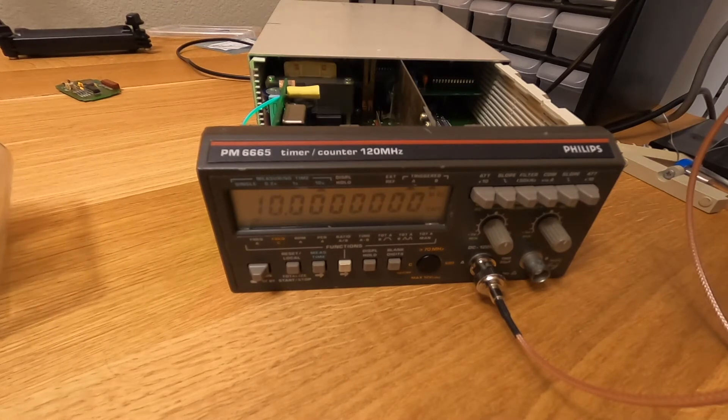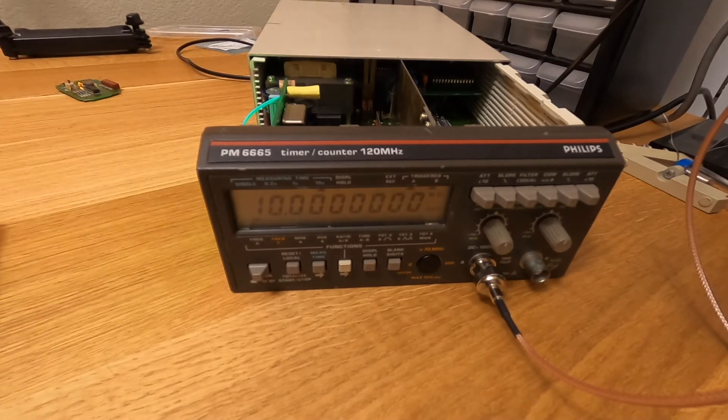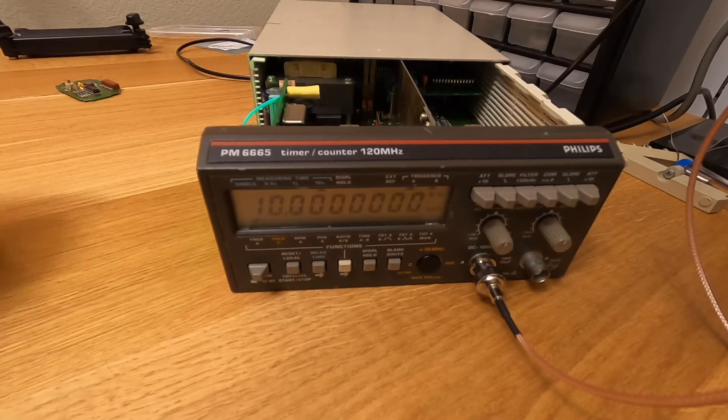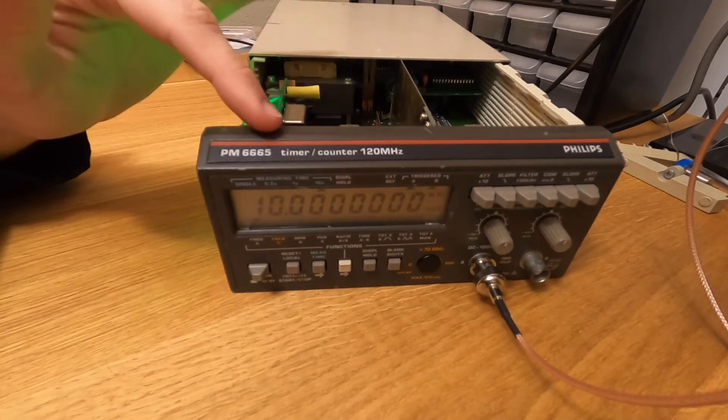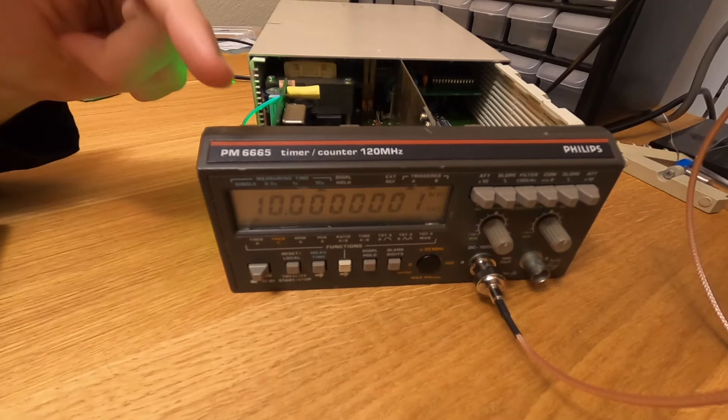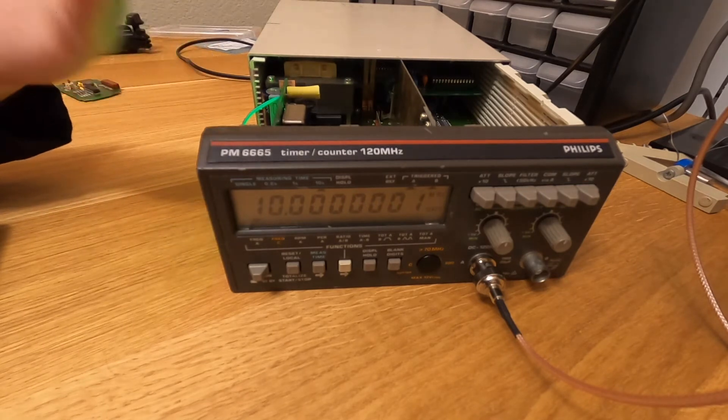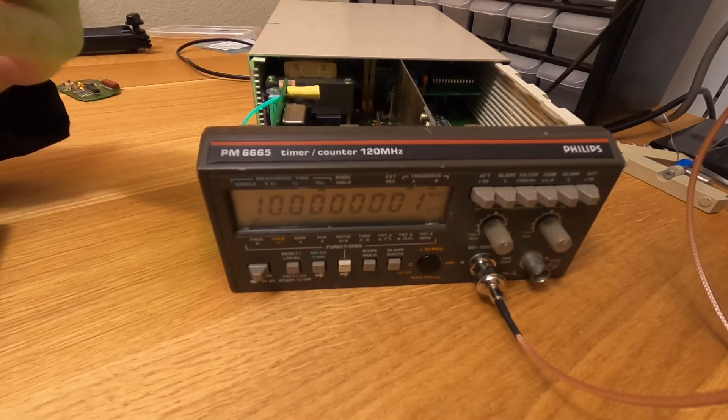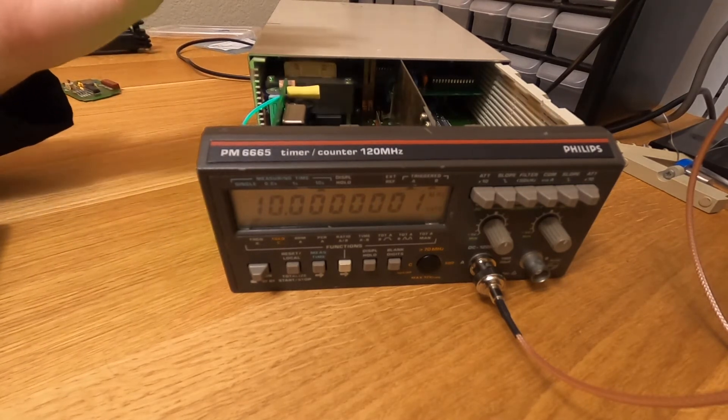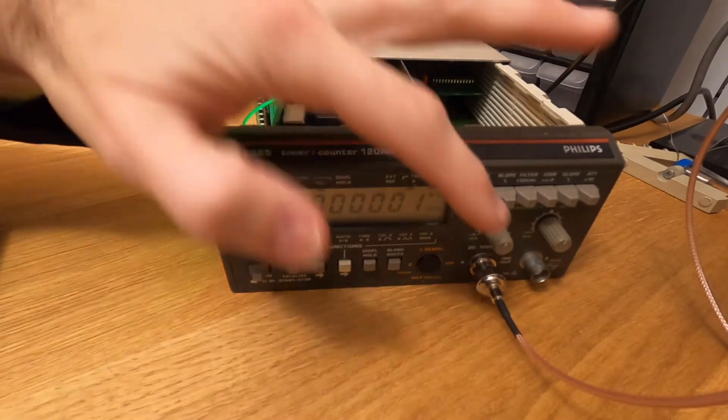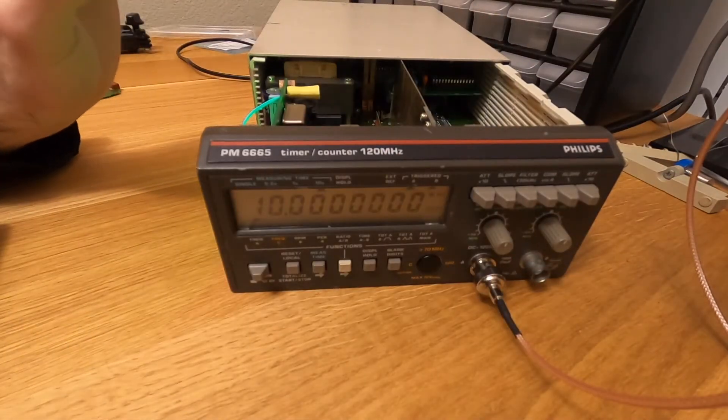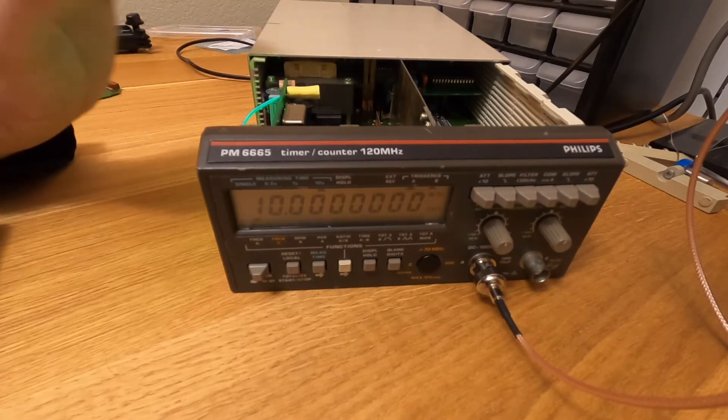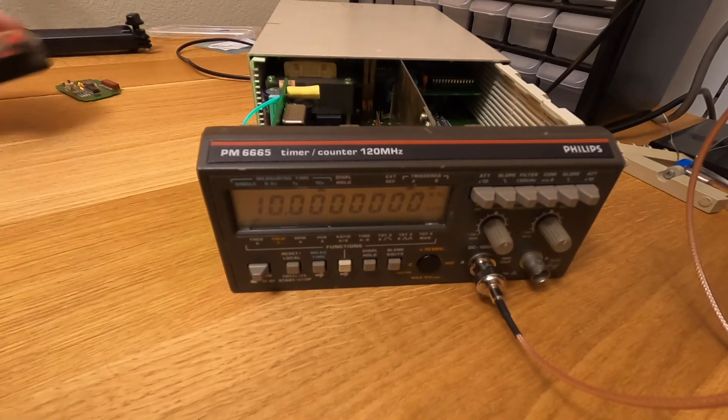So what I'm going to do now, is I'm going to use an oscilloscope to look at the phase of the internal clock and compare it with the phase variation of a reference, such as my GPSDO. And that will allow me to have a very, very fine-tuned calibration. So let's do that now.